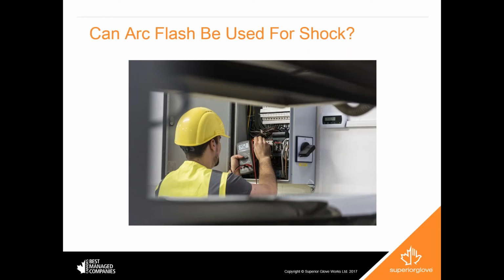One other thing I'll add there, Matt: I was at a show earlier this week, and a gentleman asked a question very similar to that. For those of you who were able to see the video that we showed, that was not an arc flash. That was nothing more than the thermal burn of material, performed by DuPont in what I think they call their Thermoman test. It's about the equivalent of a 2-cal arc flash, but it was not meant to be viewed as an arc flash in itself. So it's important to remember the difference between those two and make sure that your product is actually arc flash tested. It should have the arc flash symbol, which is the triangle with what I'll call a little explosion-looking diagram in the middle of it, and give you a rating out to the side.